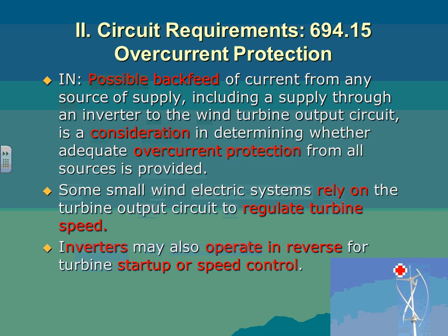I've never installed them, but I've seen a lot of systems where it goes both ways. You take power from the grid to start the turbine, and after the turbine is started, it feeds back into the grid. So if you're using the output as part of regulating your speed, then you have to pay a lot of attention to even having a disconnect for the turbine, because if you disconnect the turbine and its output is controlling its speed, you will overspeed and burn equipment. That's what I say, the devil is in the details when you get into the regulations.